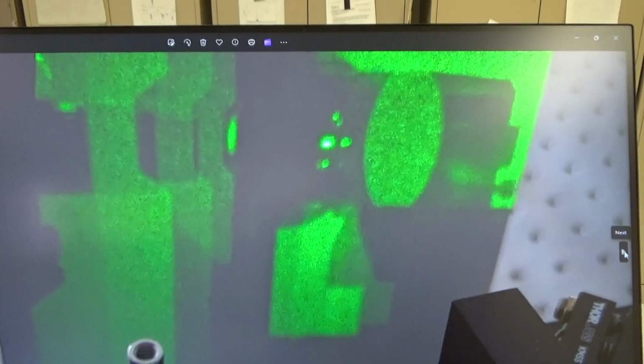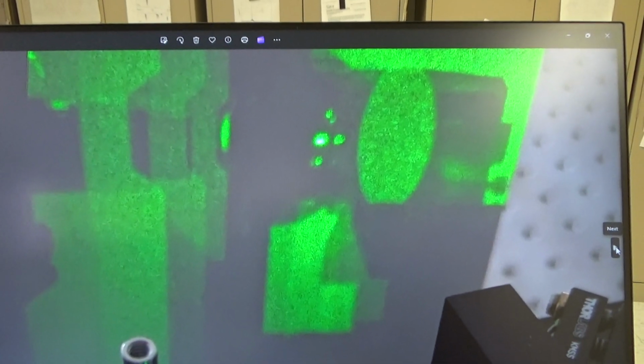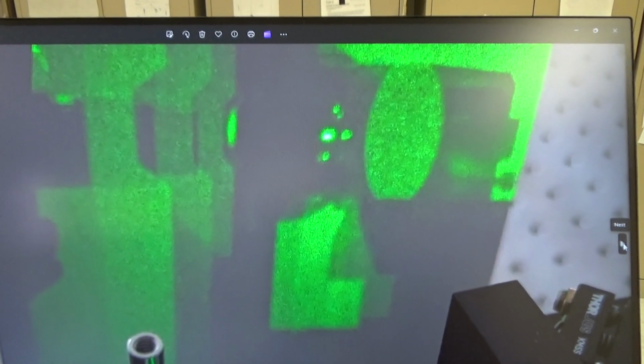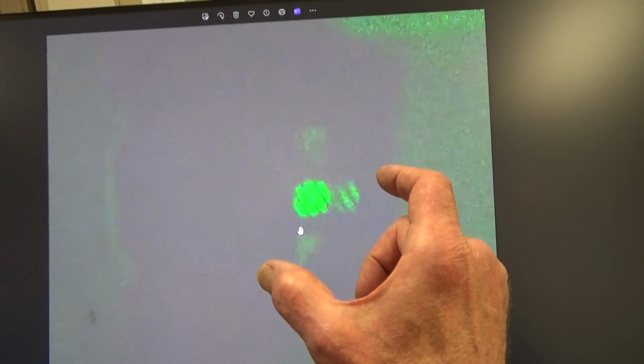If you have your injection seeder on, you can open that up and then turn that on and then open the aperture of the system, and you'll be able to see interference fringes when the alignment is very close. The fine tweaking of the rear mirror is just to adjust it so that those fringes separate out until you're at the center of the interference pattern.